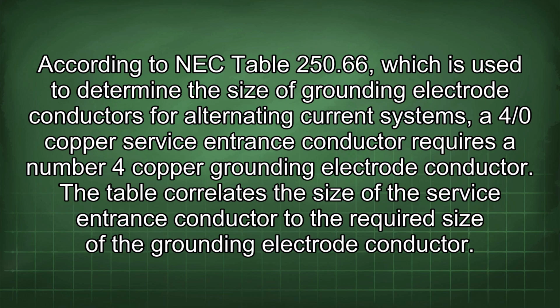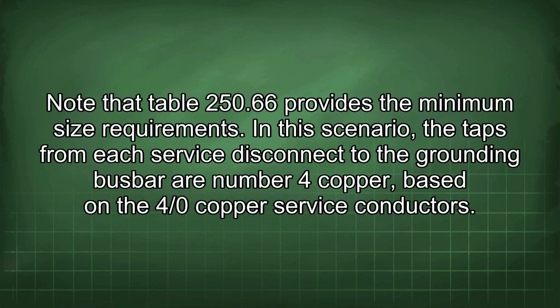According to NEC table 250.66, which is used to determine the size of grounding electrode conductors for alternating current systems, a 4/0 copper service entrance conductor requires a number 4 copper grounding electrode conductor. The table correlates the size of the service entrance conductor to the required size of the grounding electrode conductor. Note that table 250.66 provides the minimum size requirements.